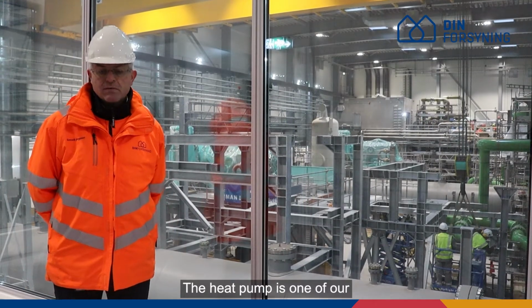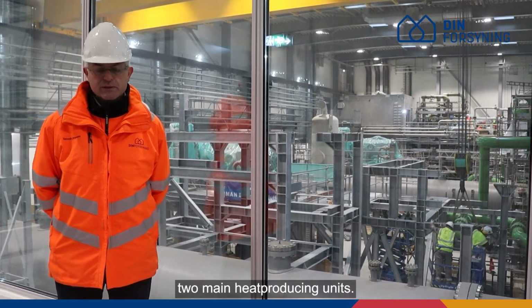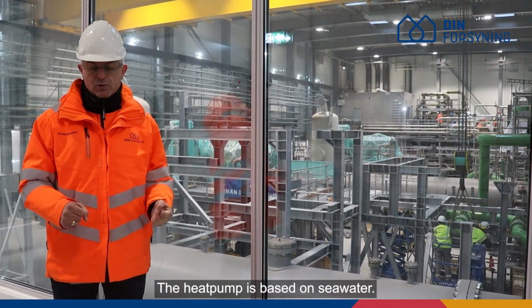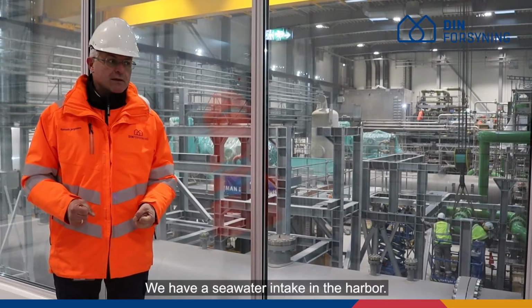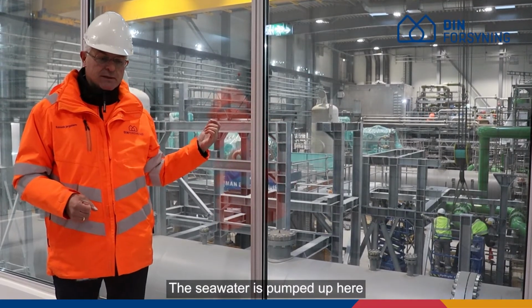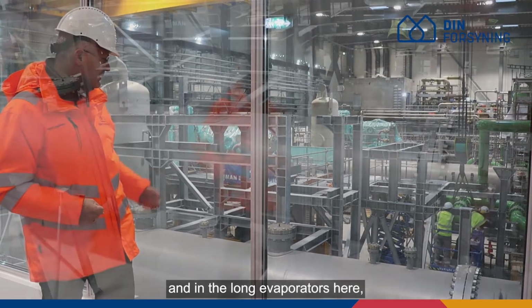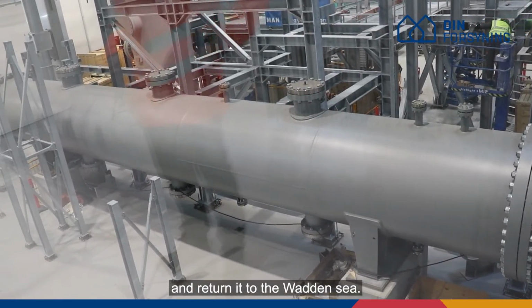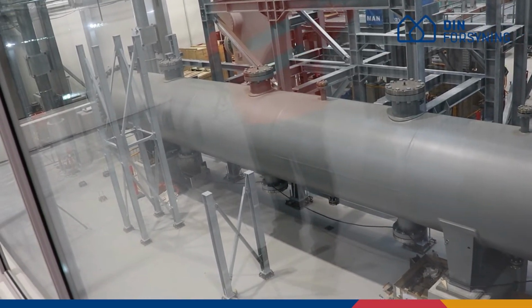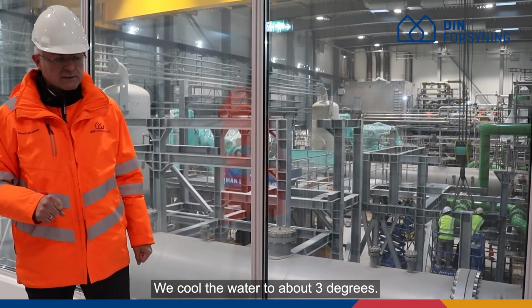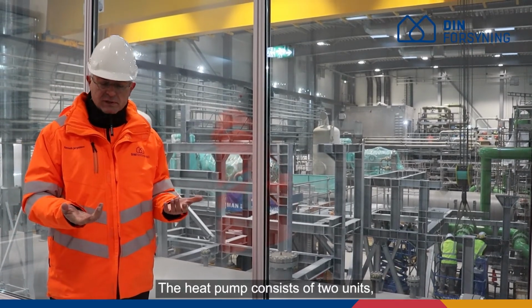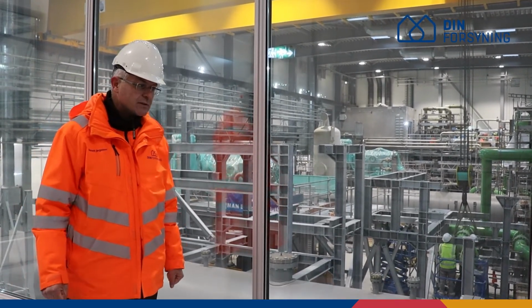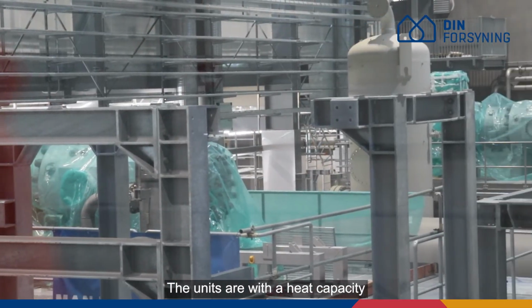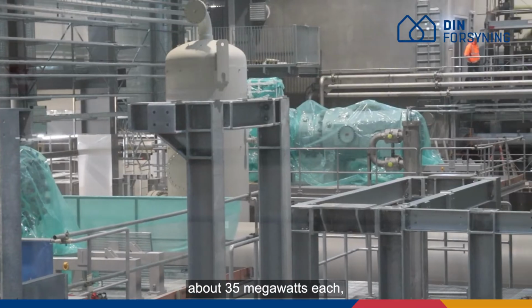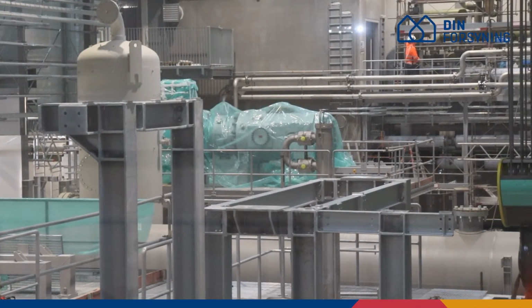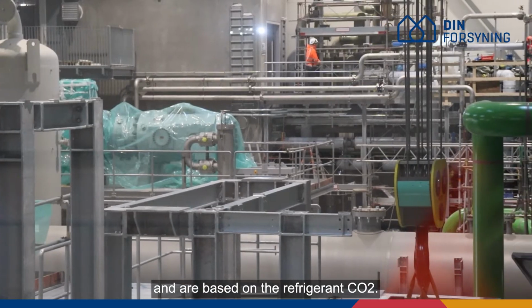The heat pump is one of our two main heat producing units. The heat pump is based on seawater. We have a seawater intake in the harbor. The seawater is pumped up here, and in the long evaporators here, we extract the heat and return it to the Wadden sea. We cool the water about 3 degrees. The heat pump consists of two units, identically built. The units have a heat capacity of about 35 megawatts each. And they are based on the refrigerant CO2.